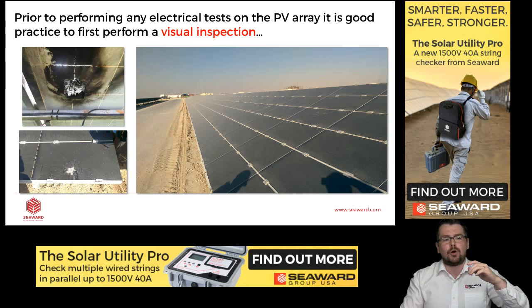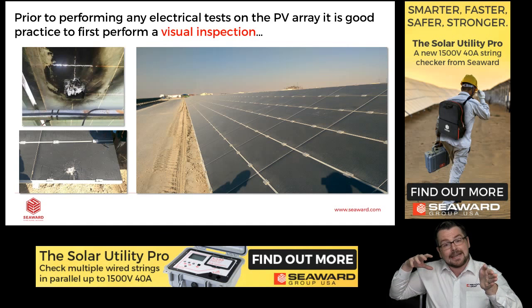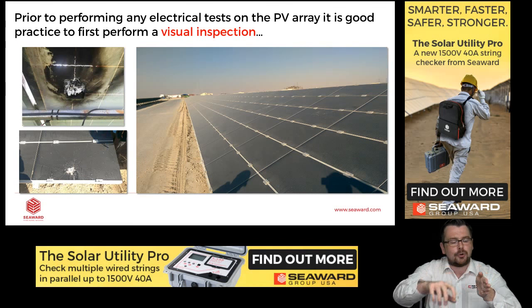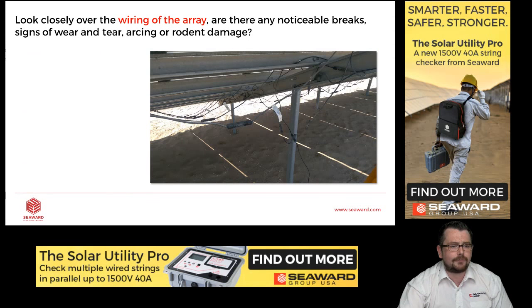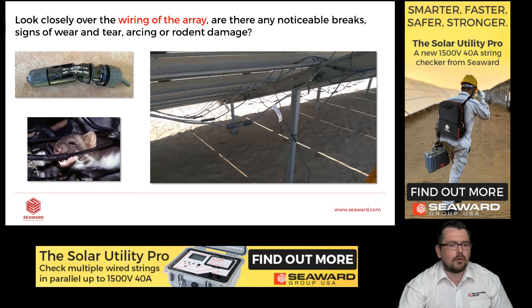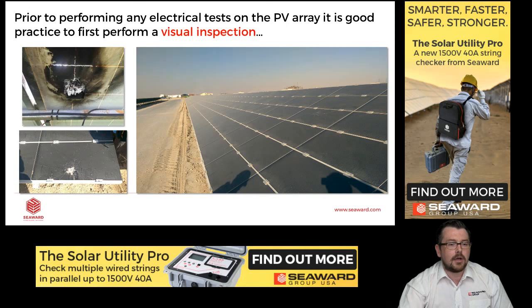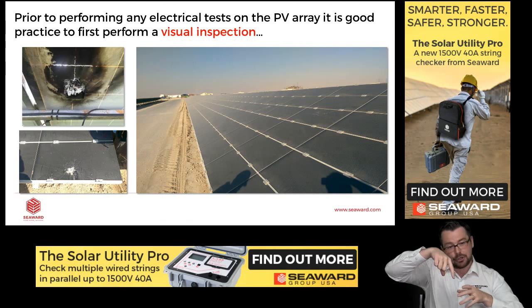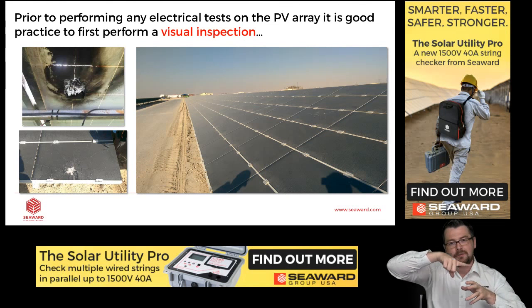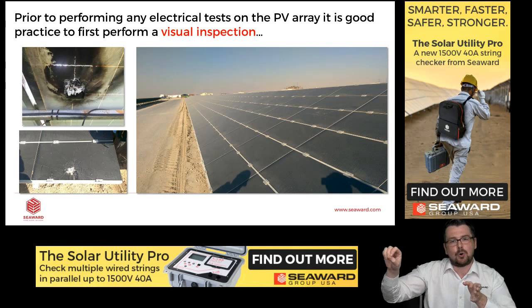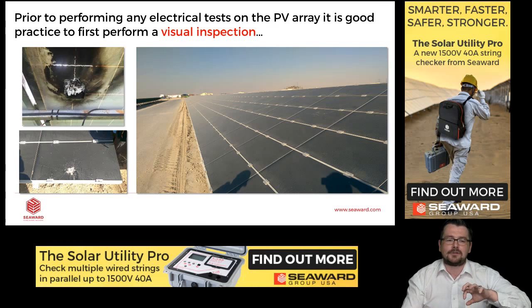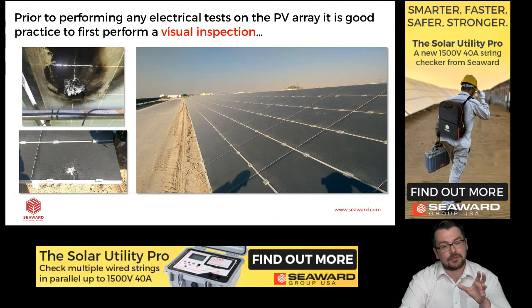But what was happening was, where the cleaning JCBs were coming through, which I have an image of, which I didn't put in, apologies. But as the machine was coming through, and you can actually see the track down the bottom of the panels, that was kicking up stones and smashing individual panels. So this was a real problem and something we should be careful of, and something we should look out for during our visual inspection.